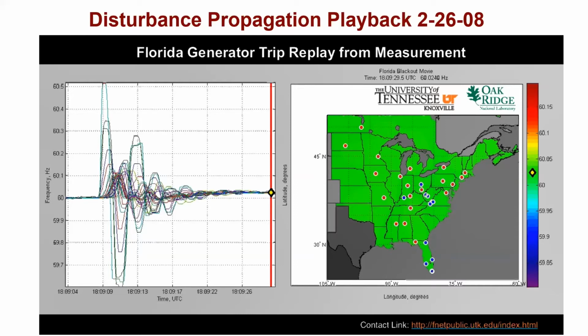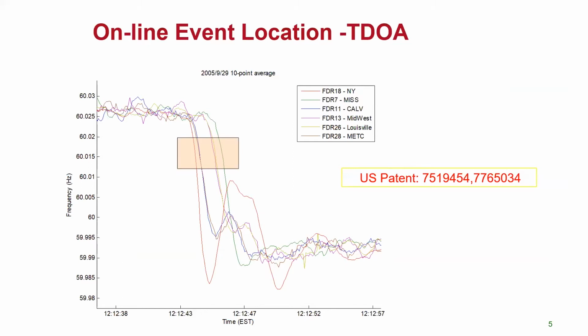And we have confirmed, yes, we do have propagation in the grid - what we call the electromechanical wave. It's a lot slower than an electromagnetic wave, but it is traveling - the speed we observe is a lot slower than the speed of light. It's like 500 to 1,000 miles per second in the Western US. The speed of light is a lot faster than that. This is because the oscillation, or the propagation, was caused by interactions between generators, which are mechanical devices in the system - so it's slow.